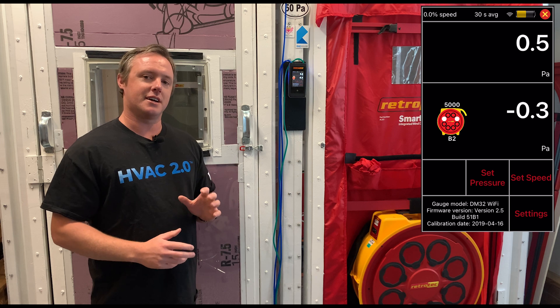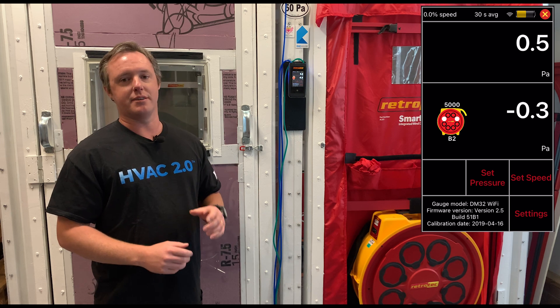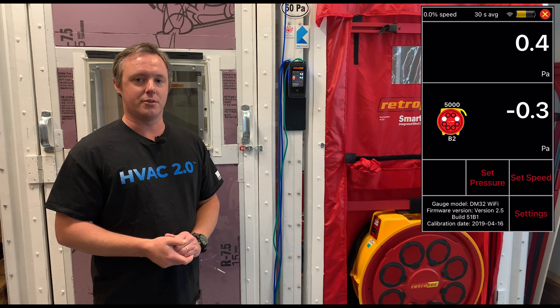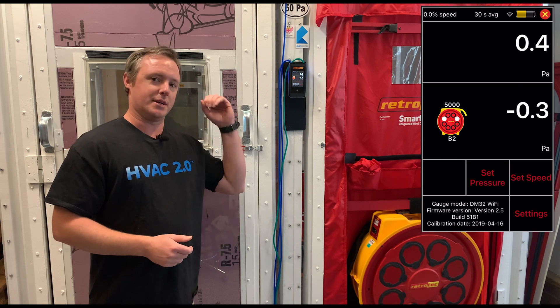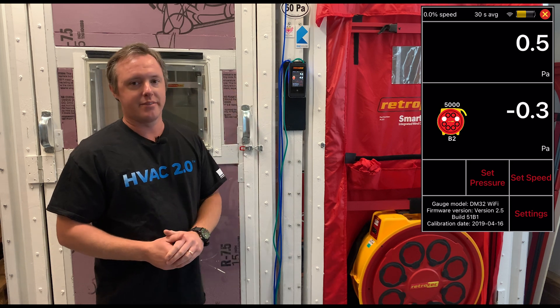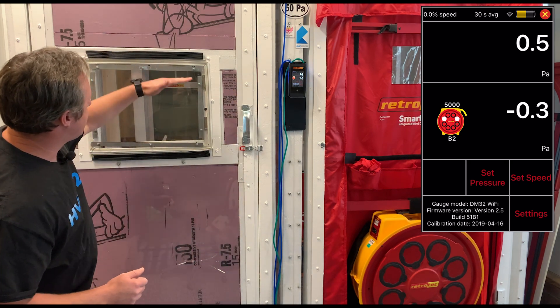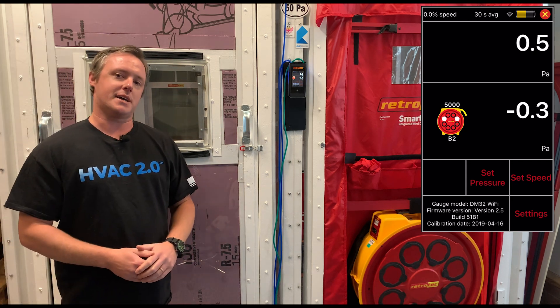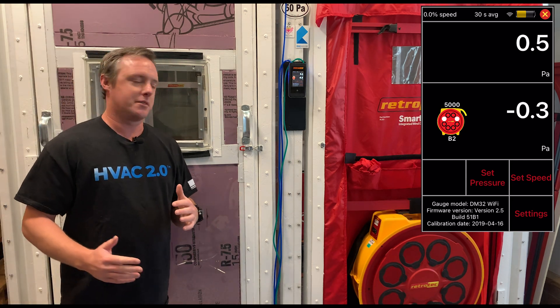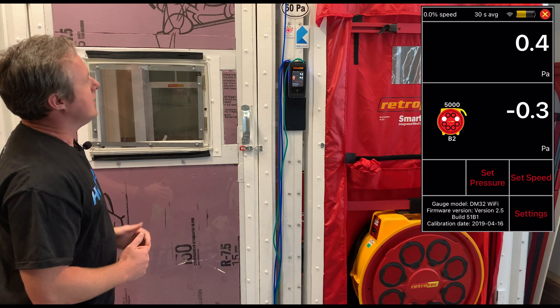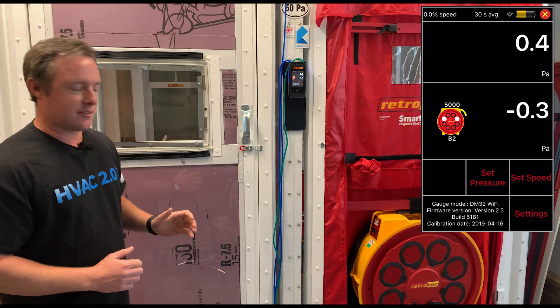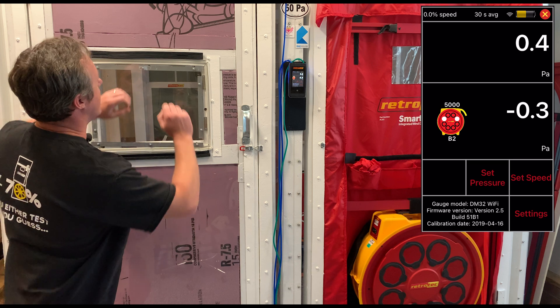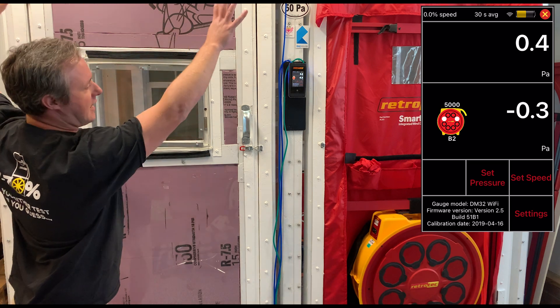Being able to measure stack effect in real time is a pretty cheap and effective way to see where the bulk of those leaks are located, whether it's going to be in the top half or the bottom half. Somewhere around halfway up the building is going to be what's called the neutral plane — that's going to be the dividing line between where air is getting pulled in and where it's exhausting off the top.